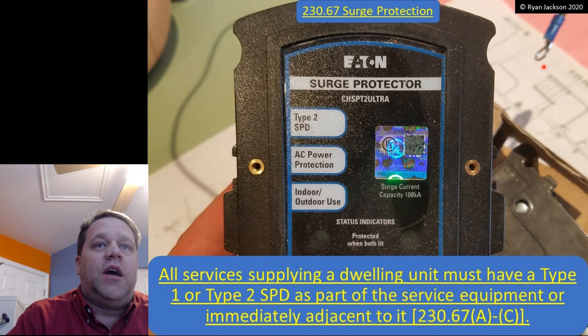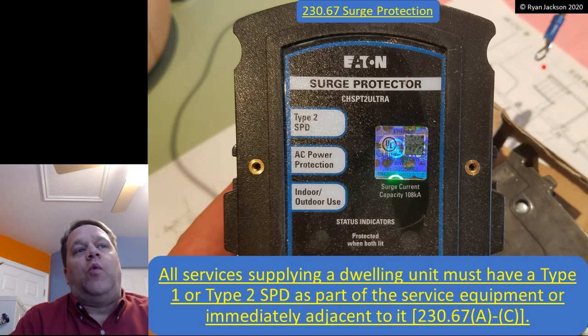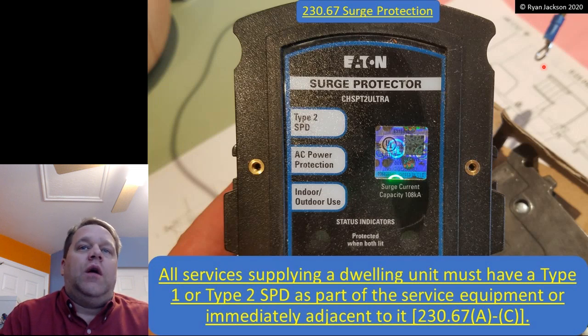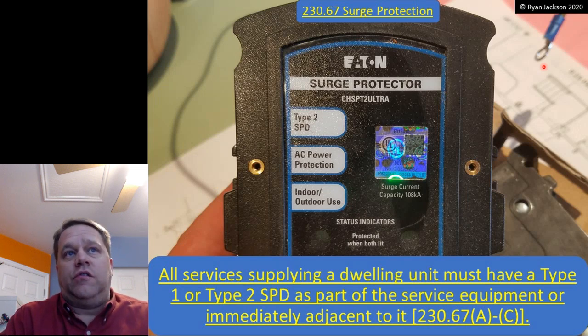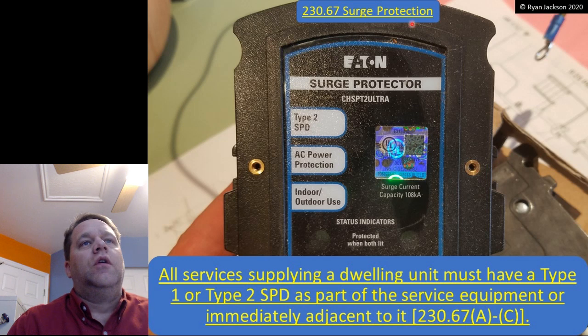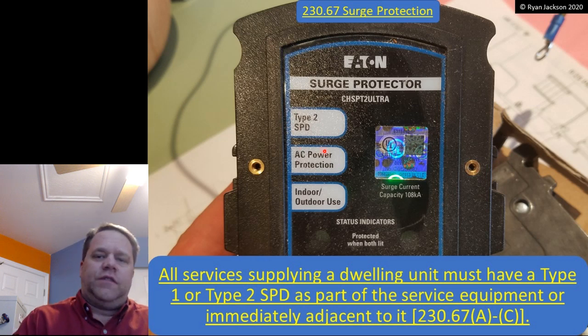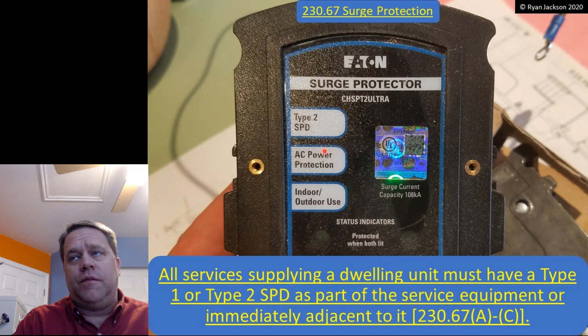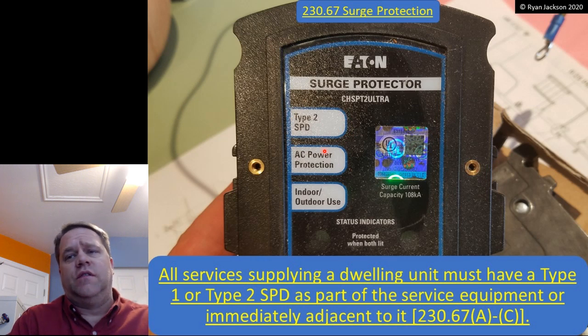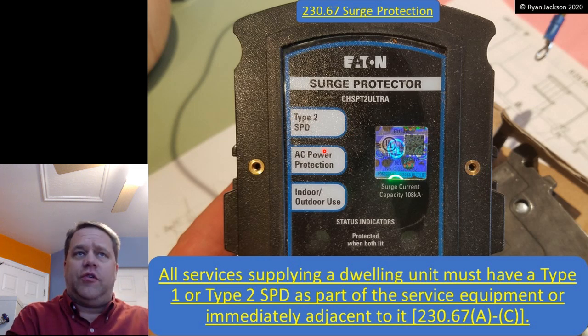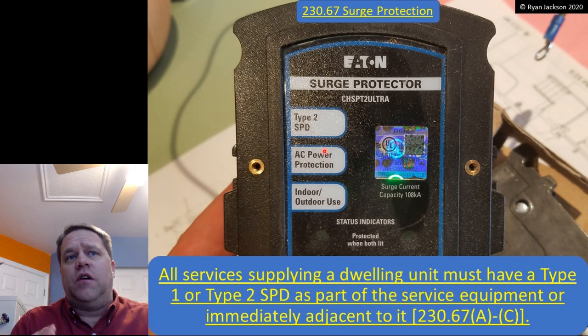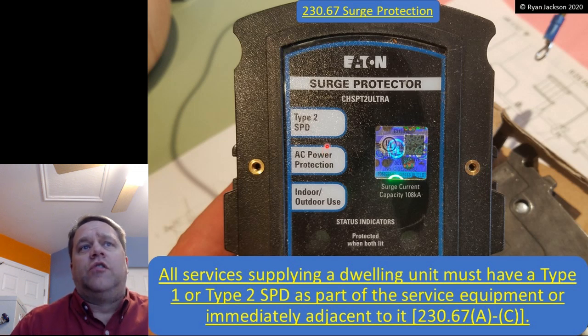All services supplying a dwelling unit must have a Type 1 or a Type 2 surge protection device as part of the service equipment or immediately adjacent to it. Okay, so this one is a Type 2 surge protection device, as we can see. A Type 2 SPD is suitable for use after the service disconnect. A Type 1 surge protection device is suitable upstream of the service disconnect.